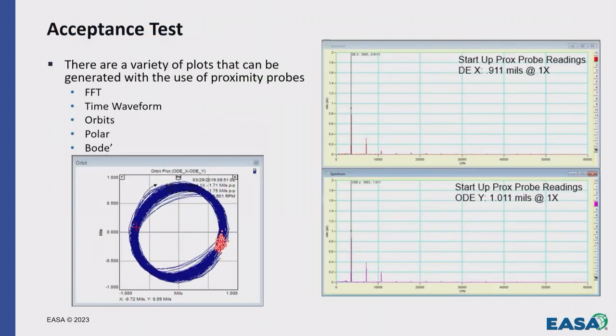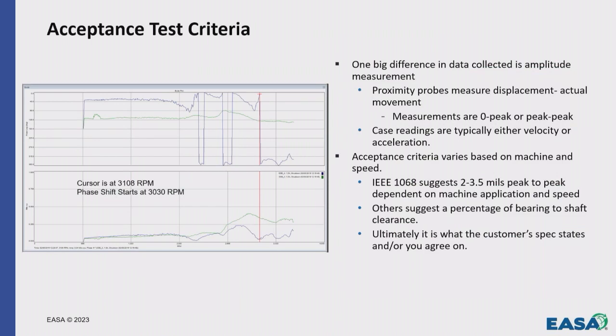On acceptance testing, it'll generate very similar plots to your typical accelerometers or anything we're doing of that nature, as well as very nice orbit plots. And as you can see on the left, that one's filtered out for 1 times and shows pure imbalance there. But this is a machine that's running very well and had a little imbalance, did some trim balancing and got it back in spec. But it also generates very nice Bode plots for those of you familiar with Bode plots. When you're trying to find a critical resonance of the rotor, not just the frame of the machine, the Bode plot is your best friend with these proximity probes.